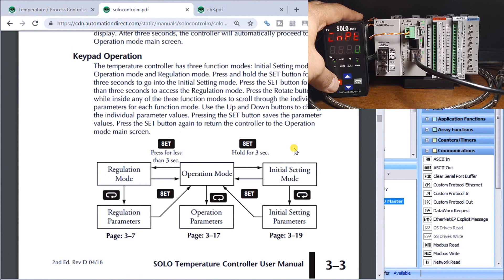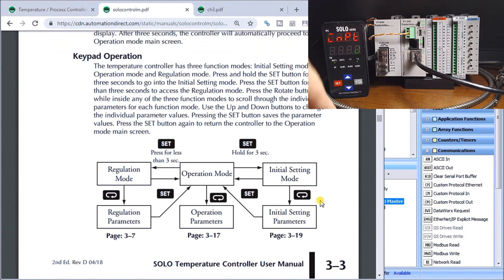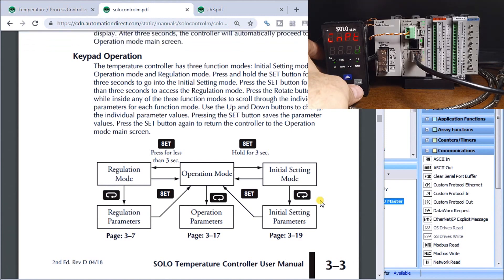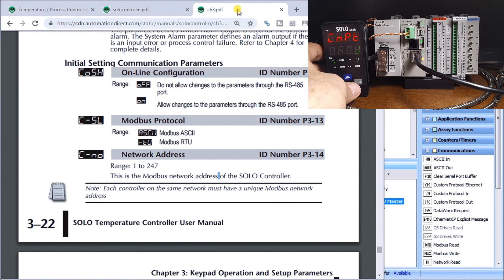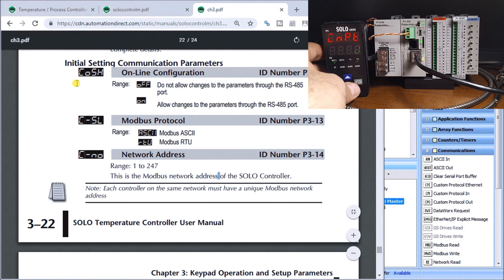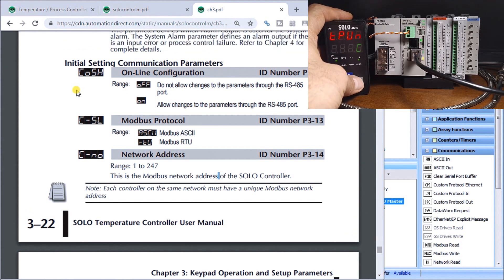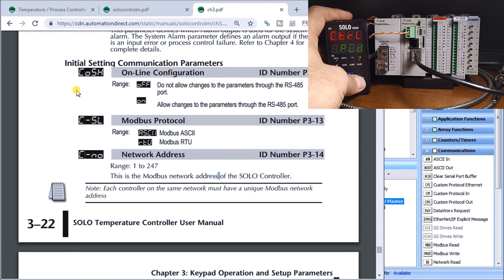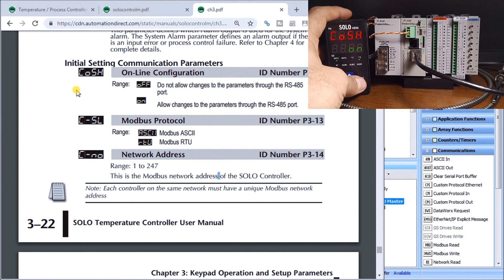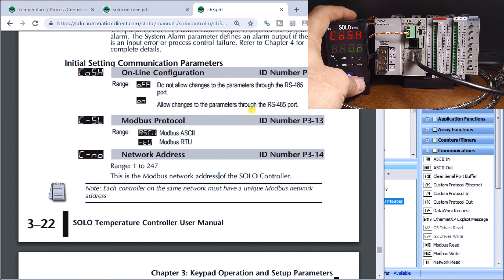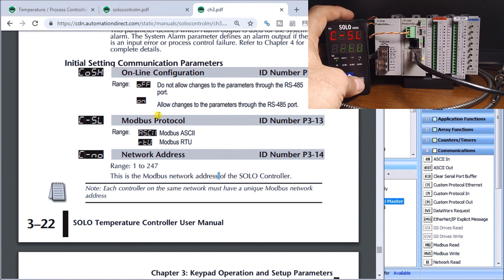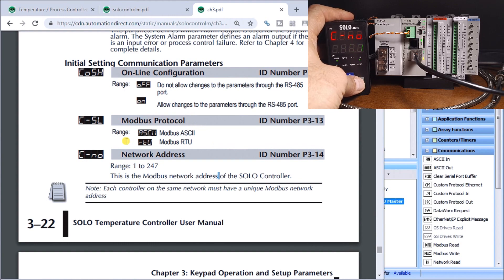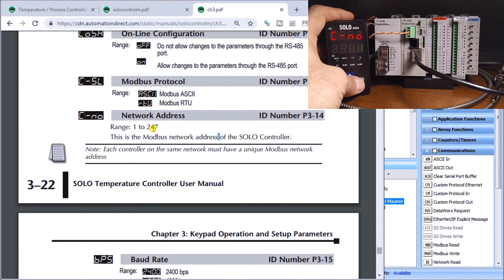That brings us into our set mode, then we can use our cycle key here in order to move through all the different parameters. Those parameters we're looking for is right here, our online configuration. Let's just cursor through, there's high and low limits, there's our PID heating, alarms, and then we get to our online configuration which is currently set to on which is what we want. Next is our Modbus protocol which is set for RTU. Next we have our network address which is set for one.